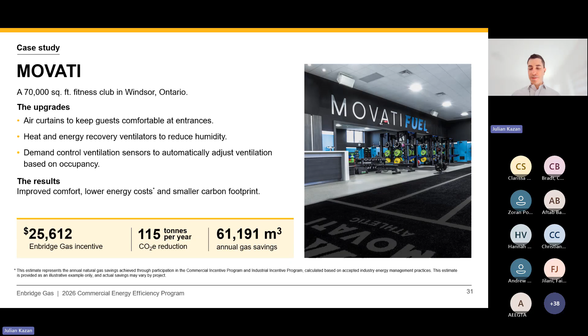They said, okay, we don't have any air curtains on the pedestrian vestibules, let's put those in and get a couple thousand dollars for that. We don't really have any humidity control, we're not recovering all the humidity in the spaces, why don't we put in some ERVs? Got a couple thousand for doing that. Didn't have any DCV, they weren't modulating their fresh air based on how many people were working out, so they put in a few DCV sensors and got a couple thousand from us. So a really simple project: they got 25 grand and ended up saving 60,000, all from just doing prescriptive measures.